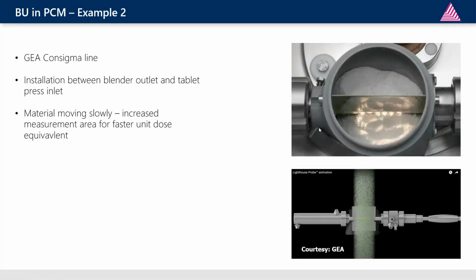Then the next position between the blender and the tablet press is quite common in the GEA Consigma lines and is based on the Centrapad FO with the central probe MS7. On the upper side, you see a view from top into the powder section, where the powder is slowly flowing along the probe with the 7 spots. These 7 spots are just illumination spots from a fiber optic probe, which is just 12 millimeter in diameter. The probe can be moved in different positions, from the measurement position to a reference position, and optionally also a washing position. Here we have a very stable powder presentation, usually controlled by level sensors, and a very constant and defined product amount measured. There are a few more slides coming about that topic later on.